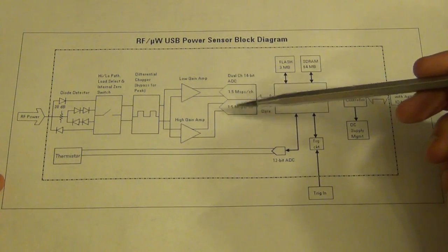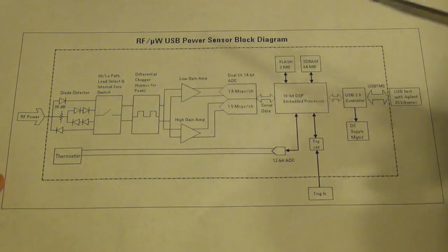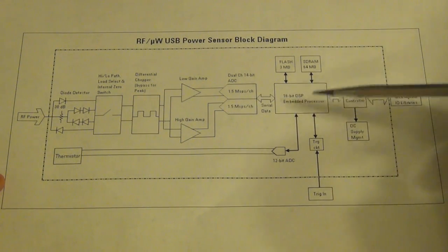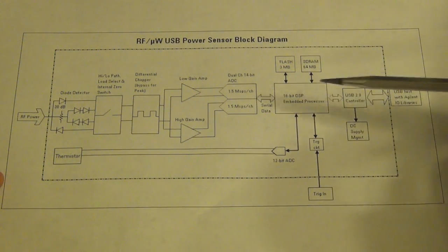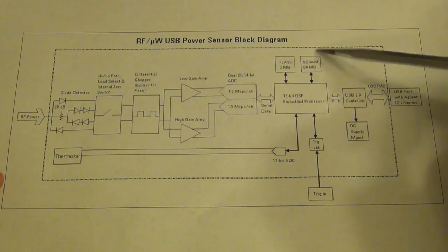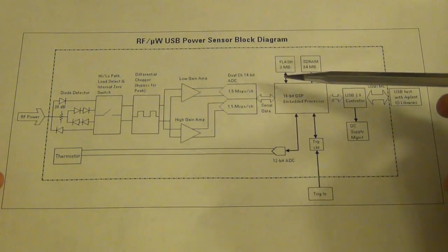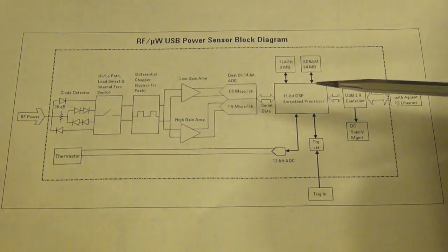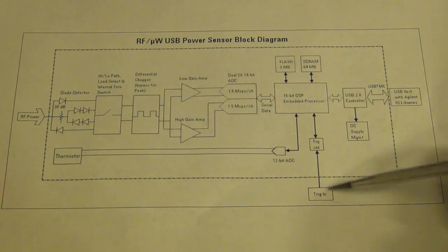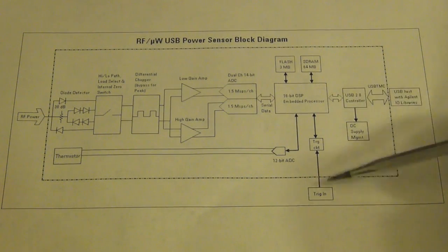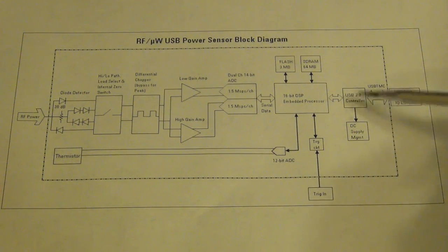The signal from the two 14-bit ADCs is sent to a 16-bit DSP processor that handles all the computation and calibration and does all the fancy things it needs to do. It has flash memory, SRAM memory, is quite fast, has peak detection, and the trigger circuitry is processed by the DSP as well through this path. There's also power supply, USB 2.0, and so on—all fairly straightforward.